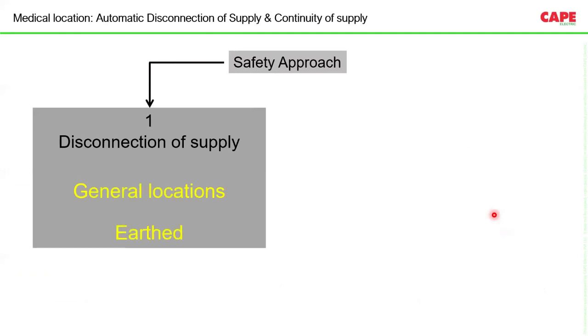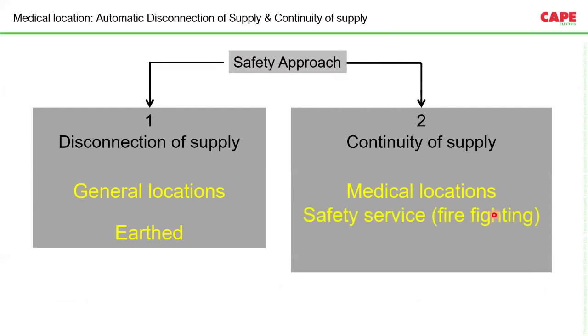Now, with respect to the concept, most of you know very well, because I am explaining this safety measure in almost every electrical safety class. There are 2 concepts. The first one is called the earthed power supply, which is for general locations where protective equipotential bonding and disconnection of the supply is mandatory. Whereas concept number 2 is for medical locations or for safety services, where unearthed supply can be used.